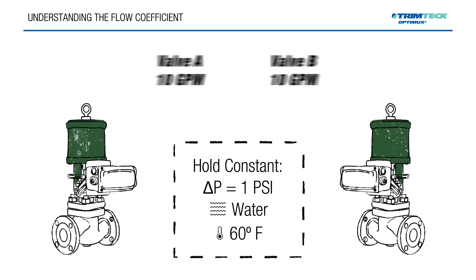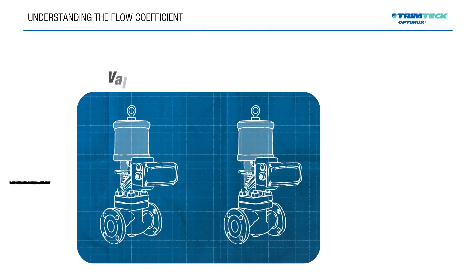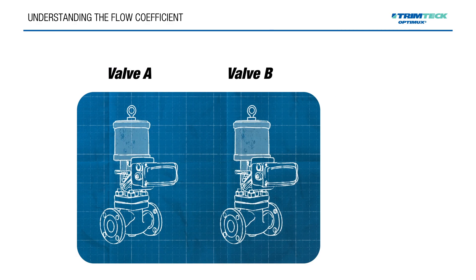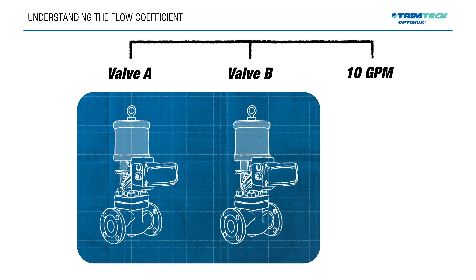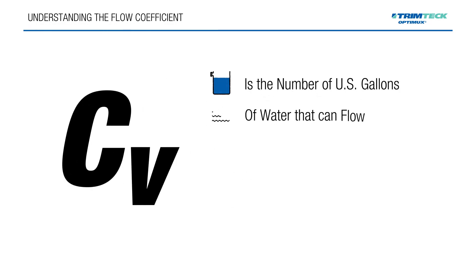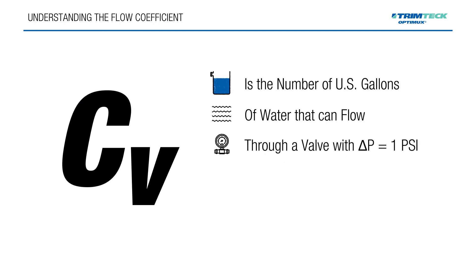We've arrived at identical flow rates. Both Valve A and Valve B share a rated CV of 10, ensuring identical performance under the exact same conditions. In conclusion, CV is the number of U.S. gallons per minute of water that can flow through a valve with a 1 psi pressure drop at 60 degrees Fahrenheit. This key metric helps ensure proper valve selection and system performance.